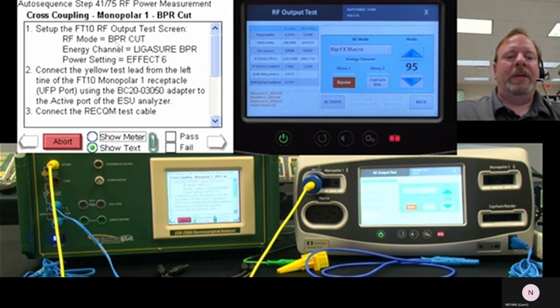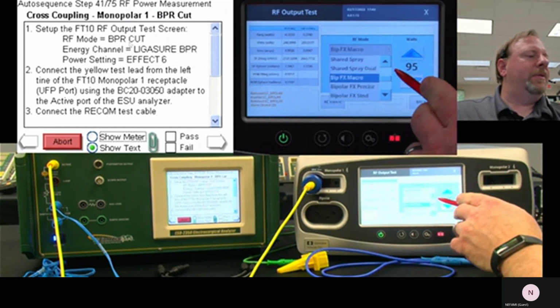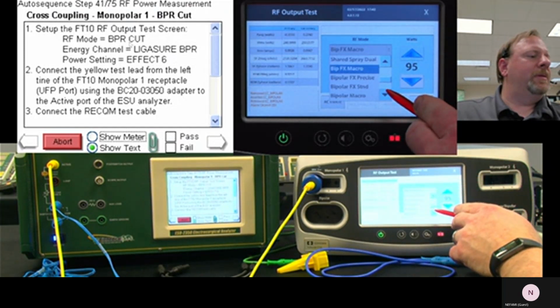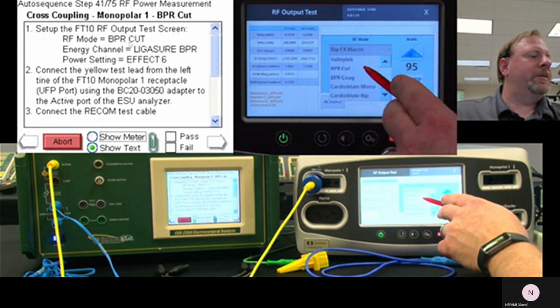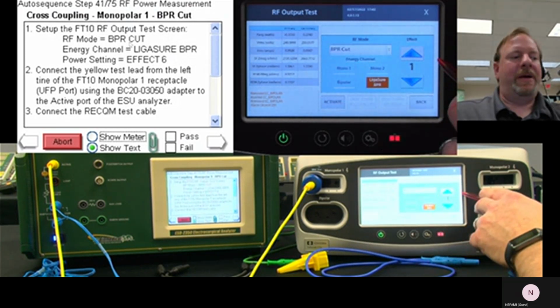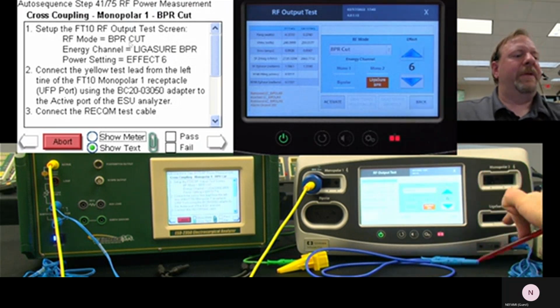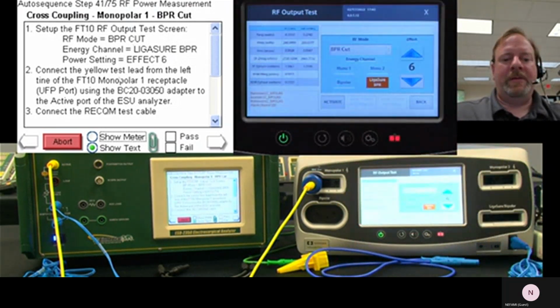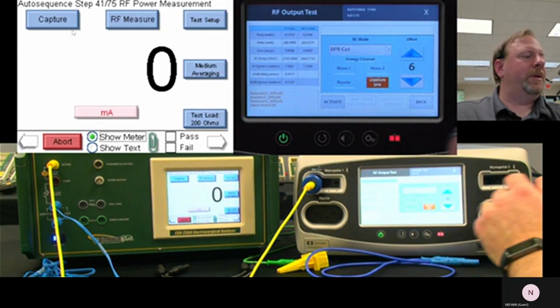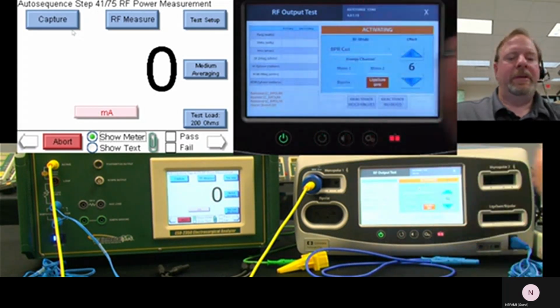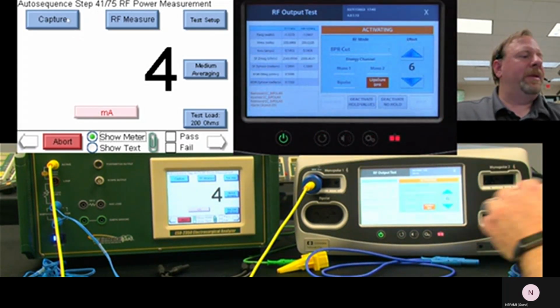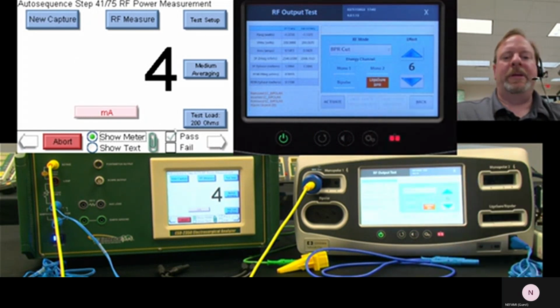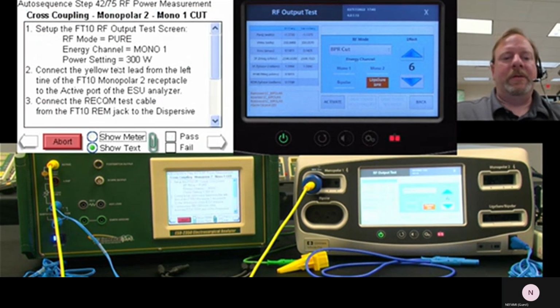Set up the FT10 BPR cut. We're going to do another output. Bipolar resection cut. Max power. So it's activating this output. We're measuring over there. What's our cross coupling in this case? We're going to say 4 milliamps. 4 is a good number. It all goes back to 4.